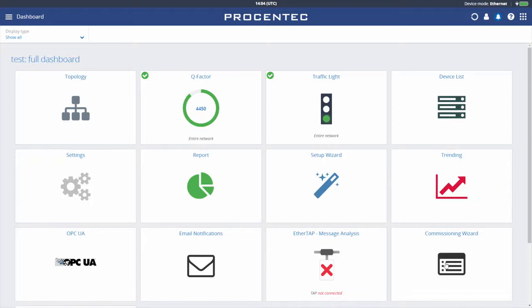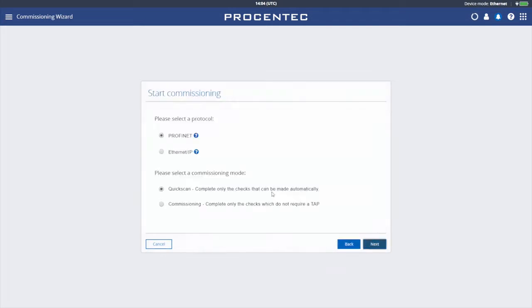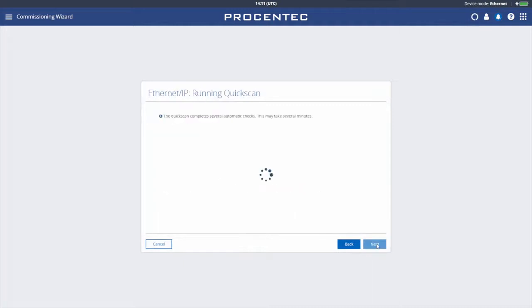Start the commissioning wizard to look for issues and select EtherNet/IP. The commissioning wizard is an optional Procentec tool that adds extra functionality. Tick off the quick scan and go to Next to perform the scan. This may take several minutes.